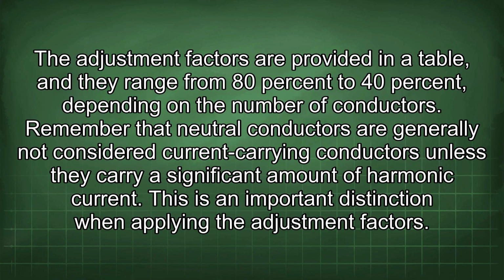The adjustment factors are provided in a table, and they range from 80% to 40%, depending on the number of conductors. Remember that neutral conductors are generally not considered current carrying conductors unless they carry a significant amount of harmonic current. This is an important distinction when applying the adjustment factors.